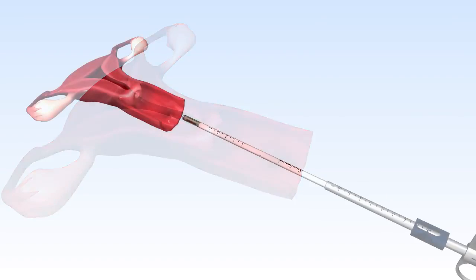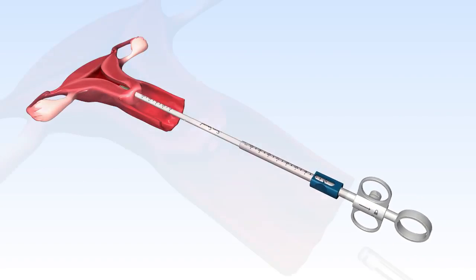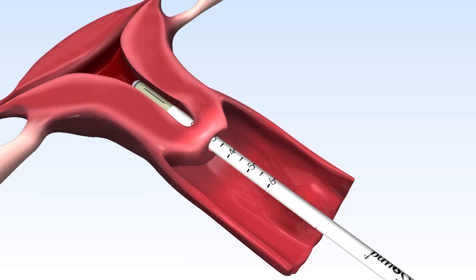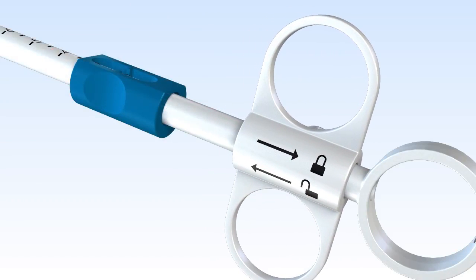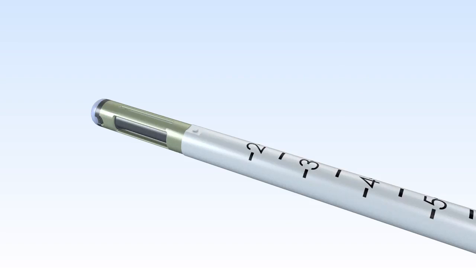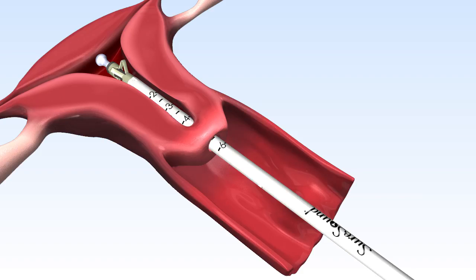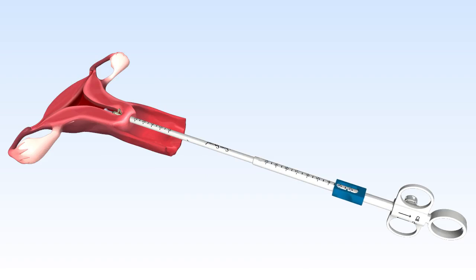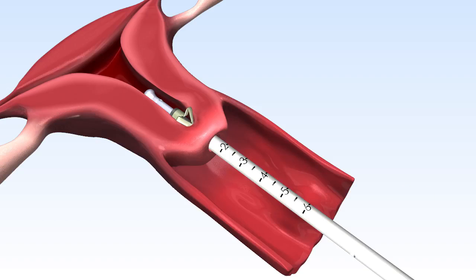Then insert the SureSound Plus transcervically, past the internal os until the distal end of the device is in the uterine cavity. Once inside the cavity, squeeze the finger and thumb rings together to deploy and lock the malecot. Pull the device back toward the internal os until the malecot meets resistance at the internal os. Slide the measurement tab distally until the inner probe reaches the fundus.